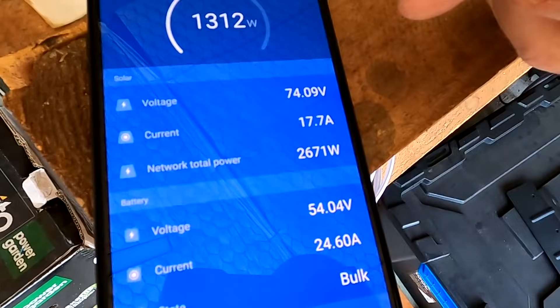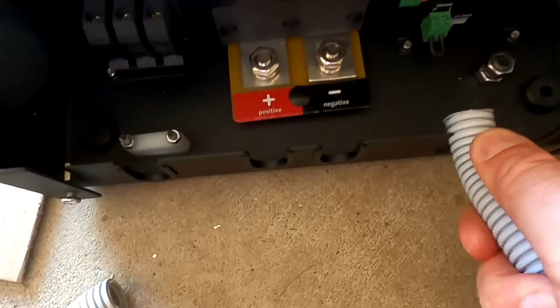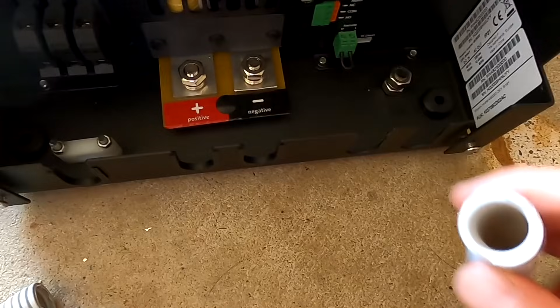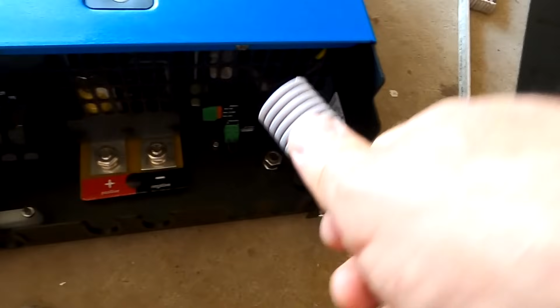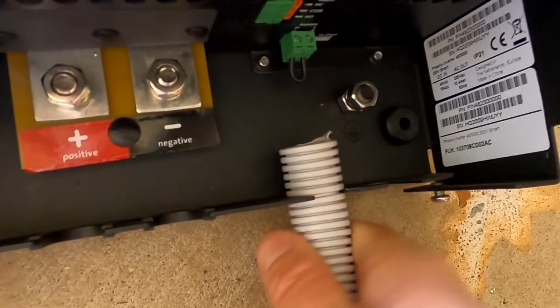2.7. Yay. So this is the 20 millimeter corrugated conduit here, and this fits perfectly into these gaps where the cables are going in. This is all good for my 240 volt, and for the VE Connect and the earth cable, this is all fine, but not for the DC input cables. This is just not large enough to fit a 35 millimeter cable. I mean, the cable just fits, but I would really like to use the 25 millimeter cable, though this one is a bit tough. I have tried to really push it in, and it works.